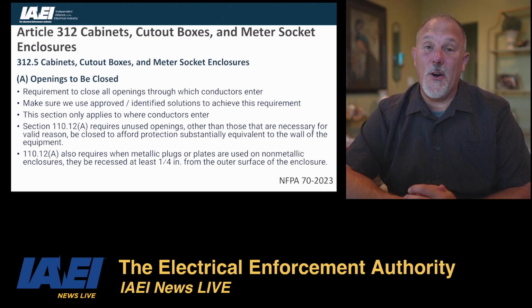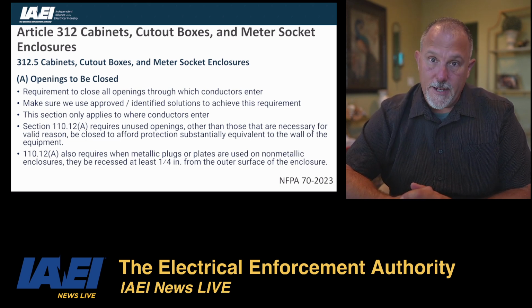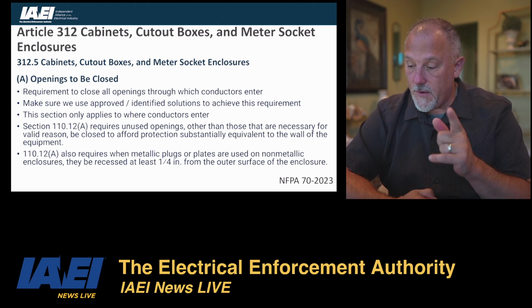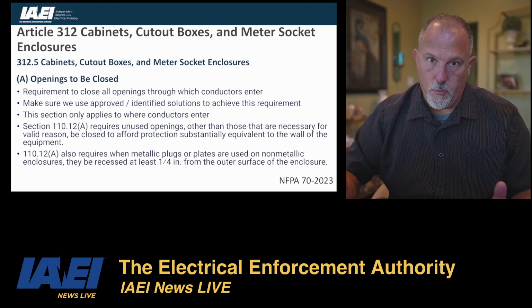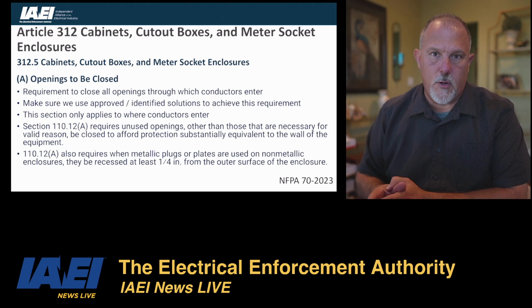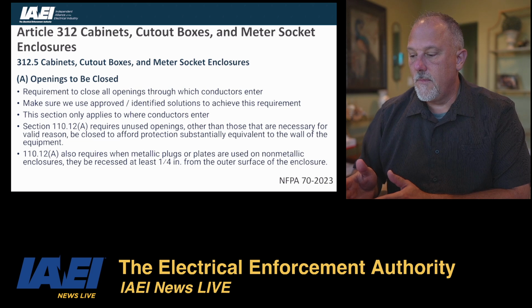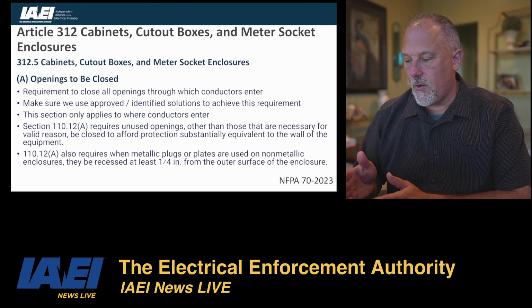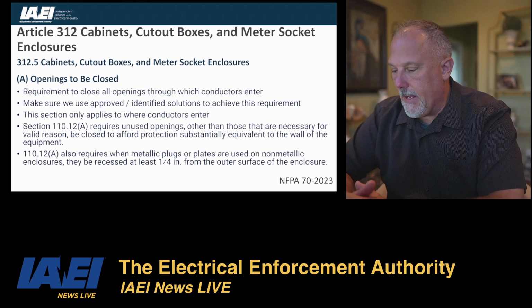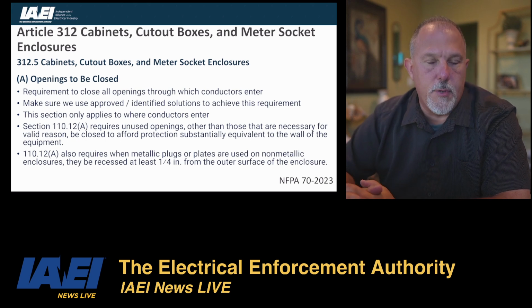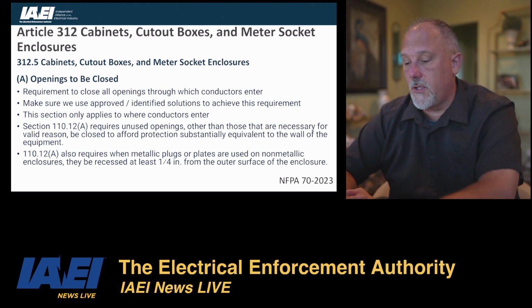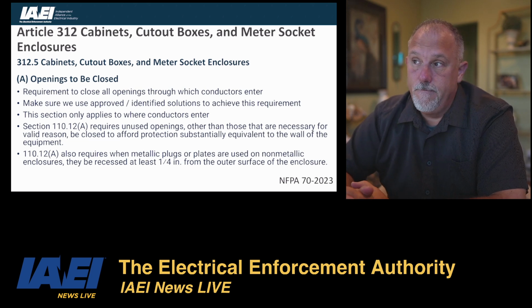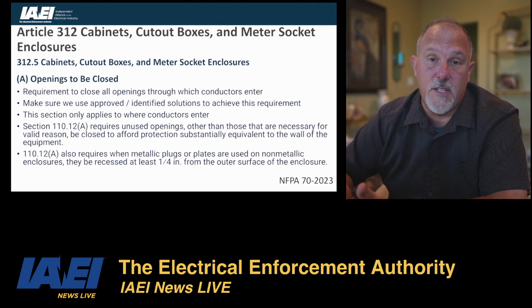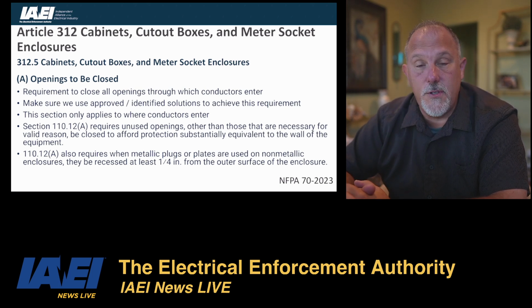The openings to be closed only applies to the conductors that enter in 312.5(A). Now, don't forget, 110.12(A) applies to all unused openings, so we cover our bases. We have the 312.5 requirement for any conductors where they enter, and then we have 110.12(A), which requires any unused openings to be closed. It also speaks to the different types of plugs that you may use and their proper installation and application, so check out 110.12(A). Hopefully there are basically two holes in that piece of equipment: one where the utility service conductors come in to the meter, and the other where those service conductors leave the meter and go to your service disconnect or your transfer switch, whatever.